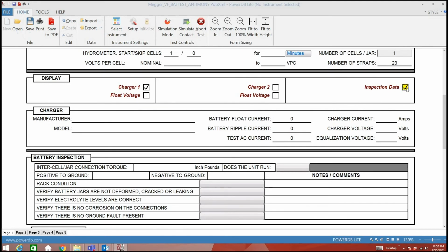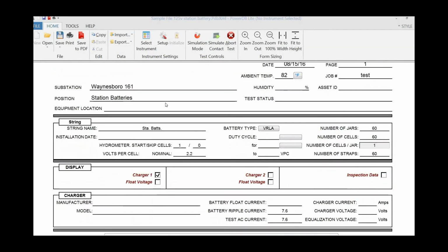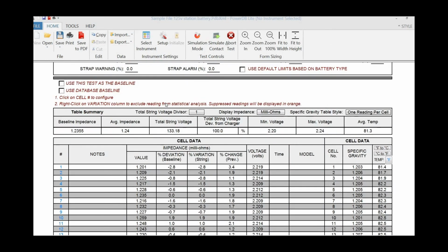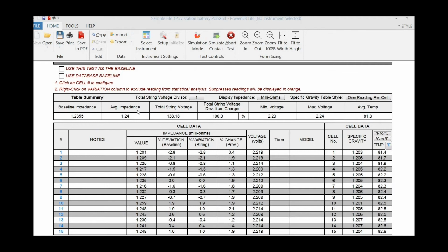To view cell data in PowerDB, simply scroll down the report to the cell data and you'll see the average impedance, you'll see total string voltage, as well as minimum and maximum voltage that were measured. Then you'll also see all the impedance values for each cell measured, as well as all the voltage values for each cell measured. And you'll also see the time at which each measurement was taken.